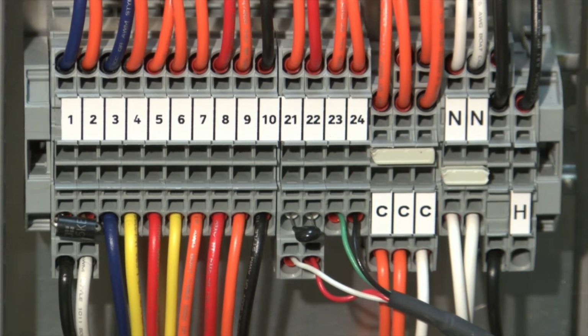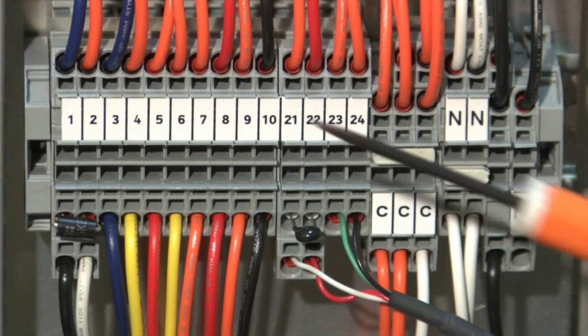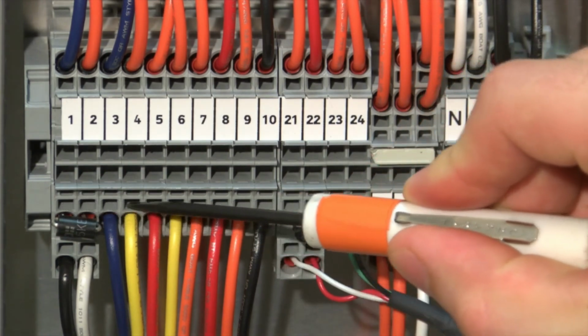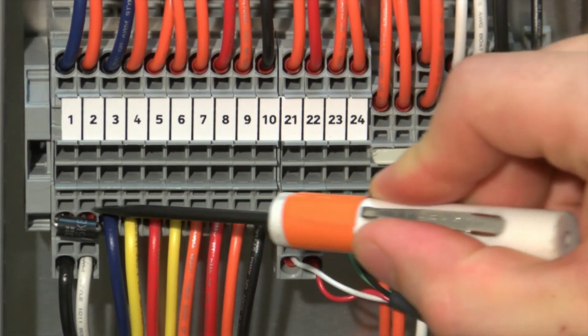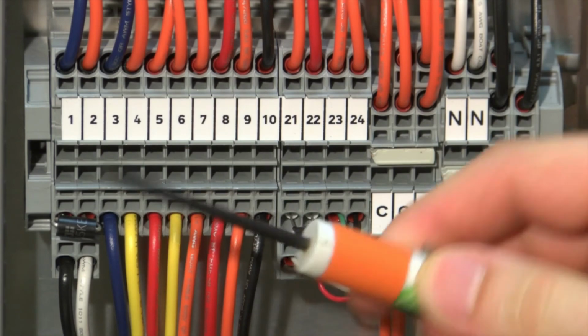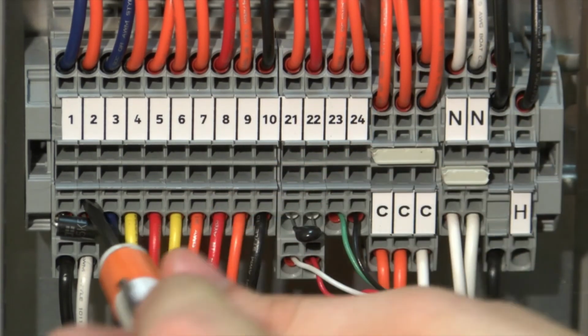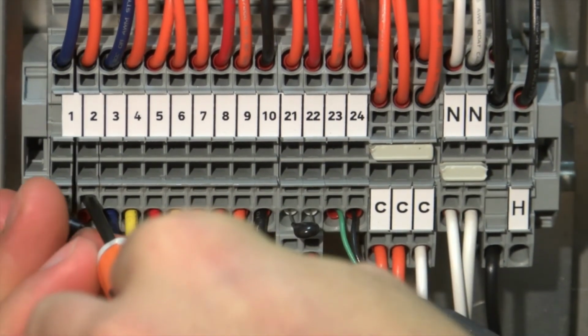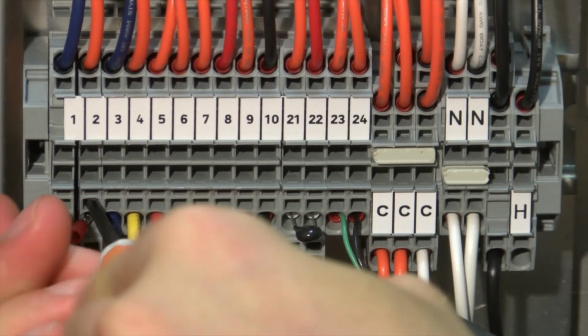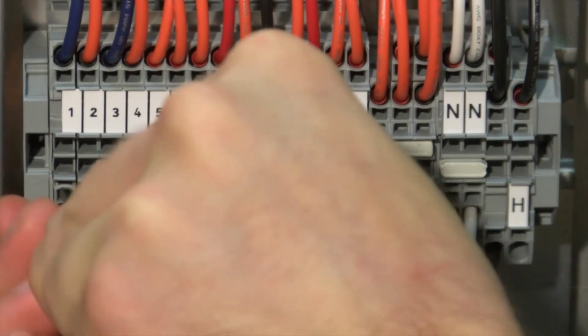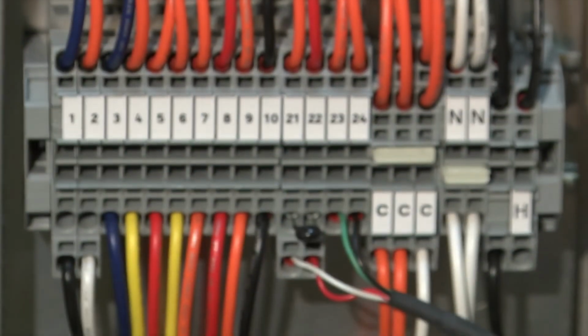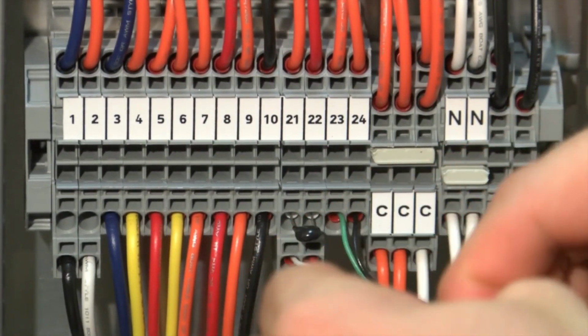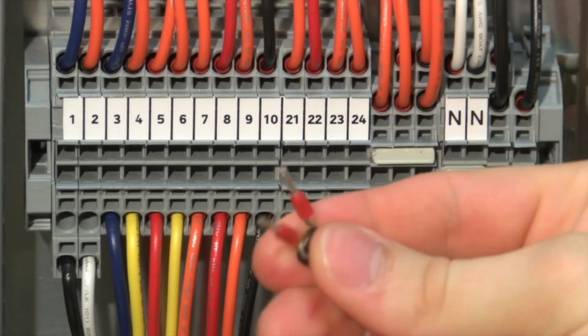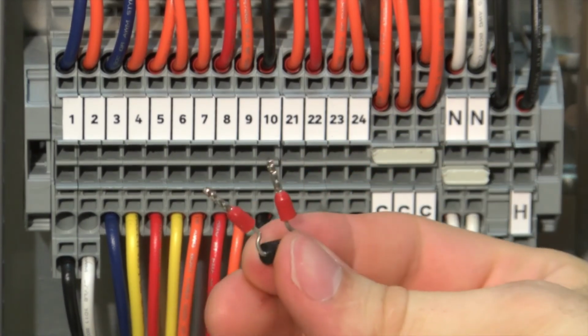To check a surge arrestor, it is best to remove it from the terminal block. To remove it from the terminal block, you will notice the small slits just above it. Using a small tech screwdriver, insert it into the block, and you can remove each side of the surge arrestor. Once you have the surge arrestor removed, we can check it.